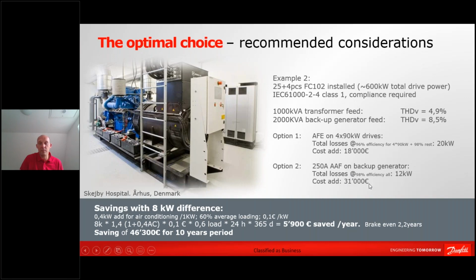And in this specific example, you pay more for the installation up front because of the added cost of the extra filter, but you will see that the saving is significant, and you will have a break even after 2.2 years, even though the installation is more expensive with the active filter compared with active front-end drives for only the bigger drives. And the reason for the saving is simply, again, the energy efficiency that you have here.